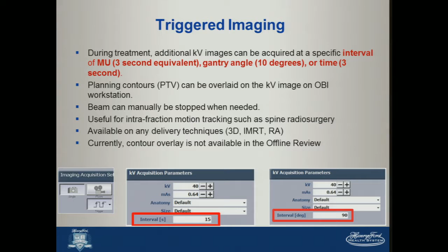Triggered imaging is imaging that you can configure during treatment and acquire KV images at specific intervals of either MU or gantry angle or time. And I believe these are the minimum values, so you can take images that are down to about 3 seconds intervals, but not below. Gantry angles are 10 degrees and time, for example, 3 seconds. So the planning contours, for example, the PTV can be overlaid on the KV image with some limitations, and the beam can be manually stopped when needed if you have sufficient image quality already. Useful for intrafraction tracking, for example, in spine radiosurgery, and available on any delivery technique.